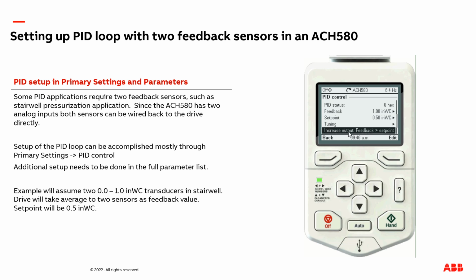We now also need to adjust how the drive reacts to the feedback signal being greater than or less than the set point. Sometimes this adjustment in the industry is called direct or indirect. In our setup, we want the drive to accelerate the motor when the feedback is less than the set point. So we need to make an adjustment here, feedback less than set point. This means the drive will increase the speed of the motor, and when the feedback signal is greater than set point, the drive will slow the motor down to a stop.